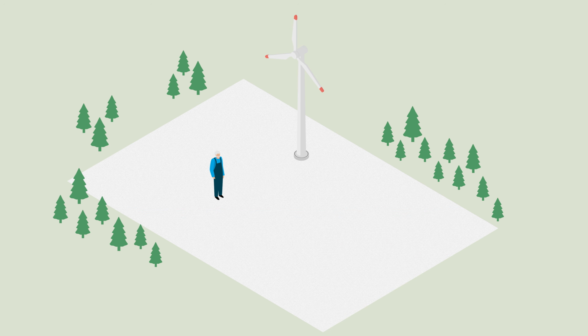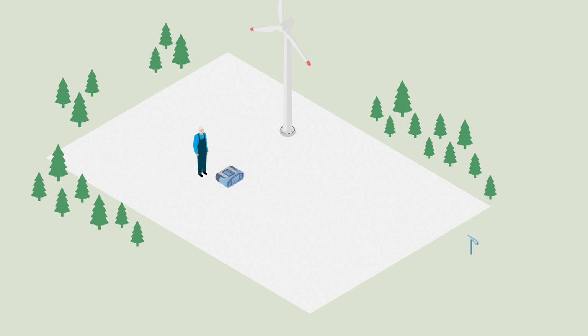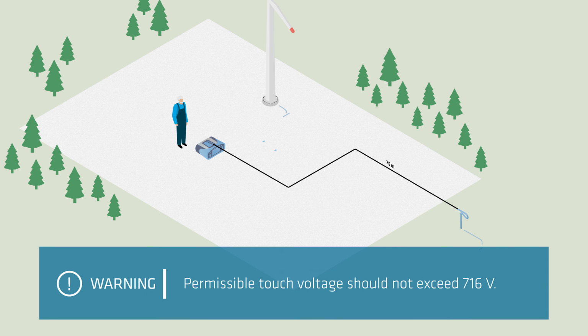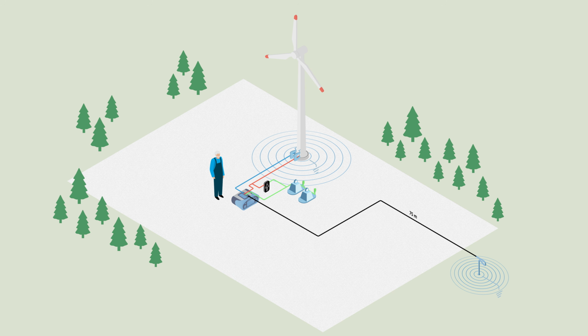Every wind turbine grounding analysis begins with the correct positioning of the remote probe. Typically, a reel with a 75-meter extension lead is sufficient to shape the voltage funnel, which is a critical element for accurate ground impedance and voltage distribution measurements. A test circuit is established between the remote probe and the base of the wind turbine structure.